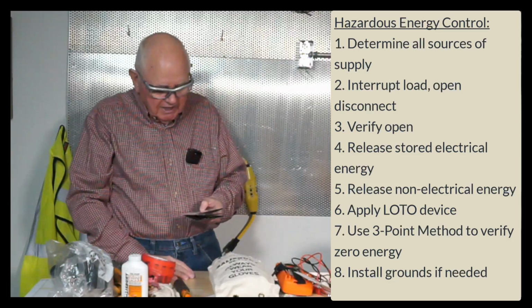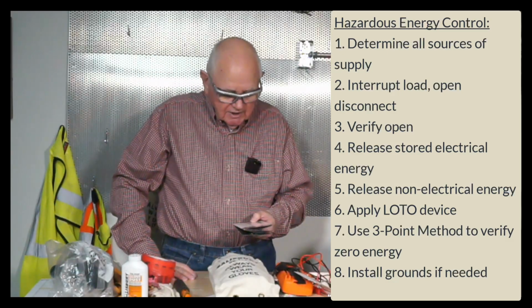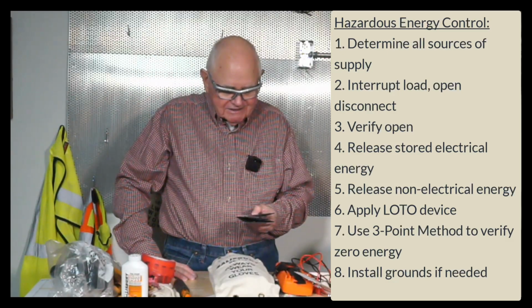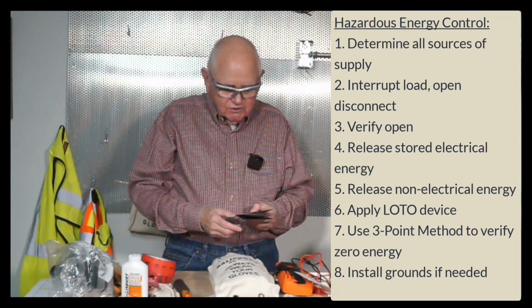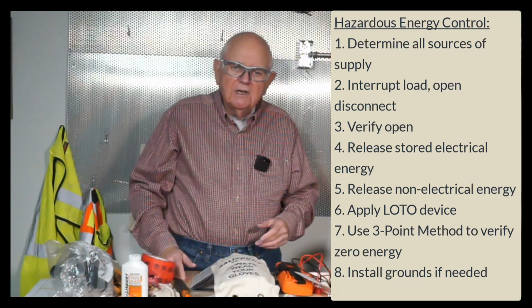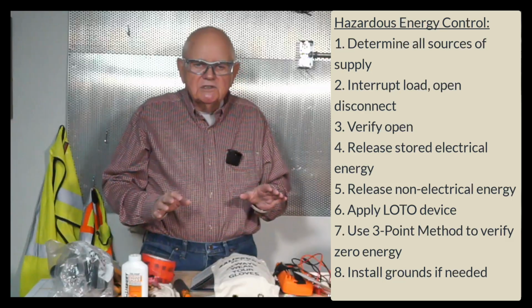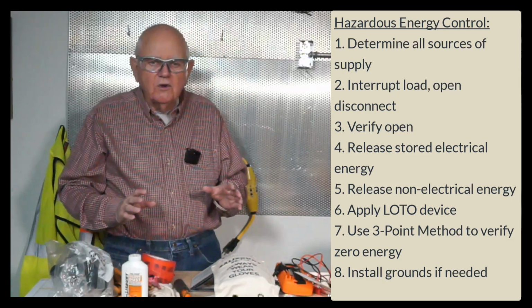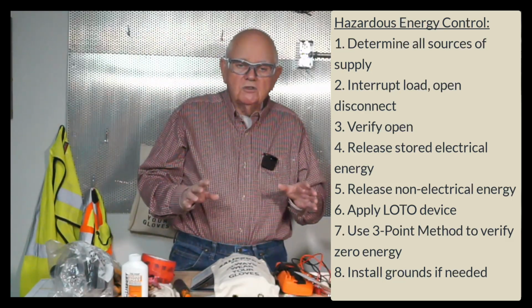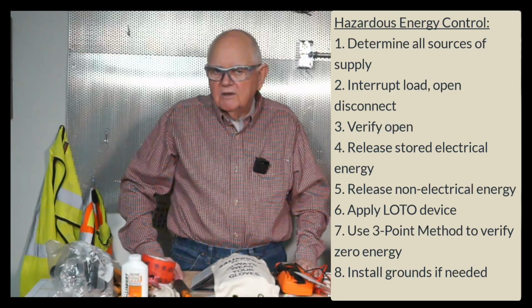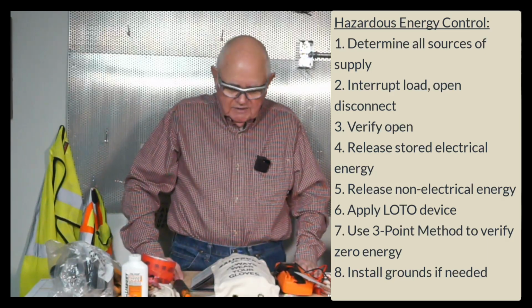And then finally, the last thing that it says in the NFPA 70E, and depending on your procedures, it says where the possibility of induced voltages or stored electrical energy exists, ground the phase conductors or circuit parts before touching them. So if needed, we don't do this a lot at low voltage, but certainly at medium voltage and above, we install personal temporary protective grounding then. So do that if you need to.